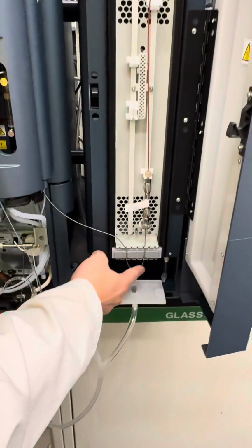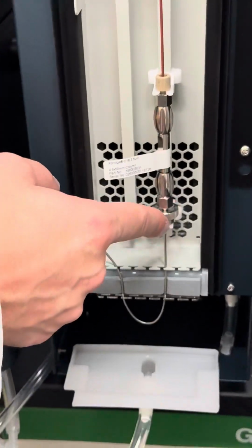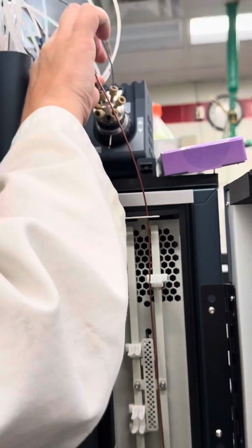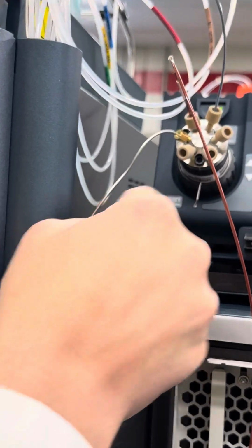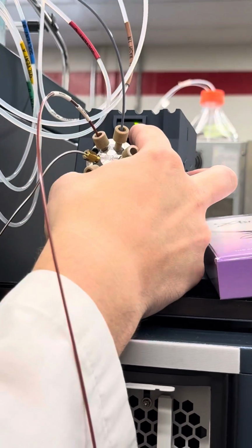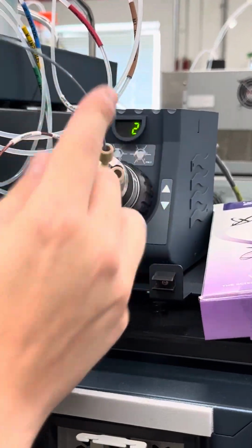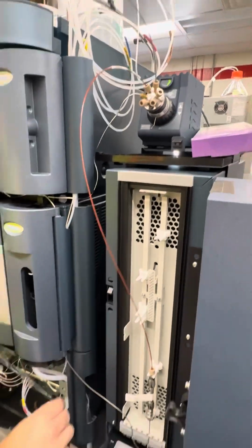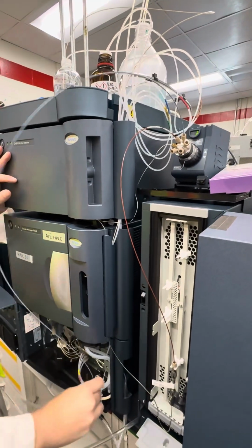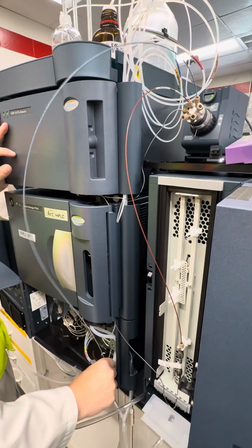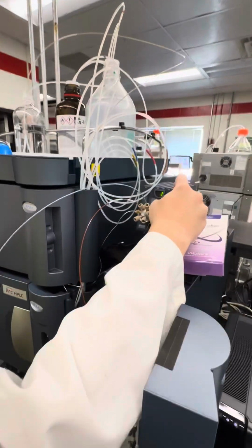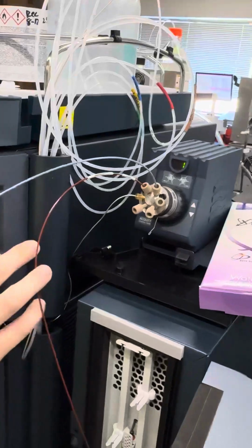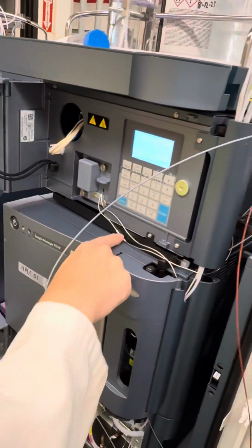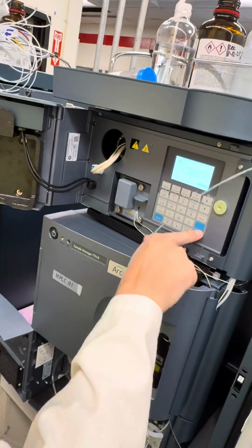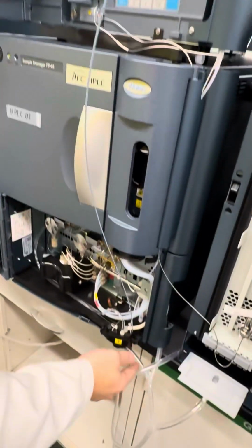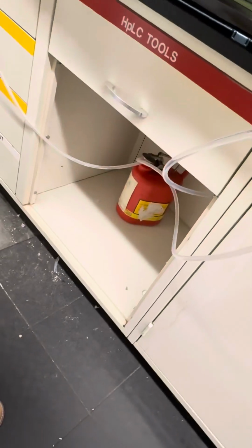Your column is right here. I'll show you how to install a column in just a second. It's gonna go up to your diverter valve. Now position 1 is gonna be to the detector. If we hit this little arrow here, it's gonna go position 2, which is gonna go to your recycle. I have it set to waste here, but you can move that up to wherever you need. So you just pop that right out. It's super easy. So we'll say, hey, we want it to go to the detector. We'll hit down. So it goes to the detector, which goes through the inlet here. And then it goes out and down to waste. So there we go.